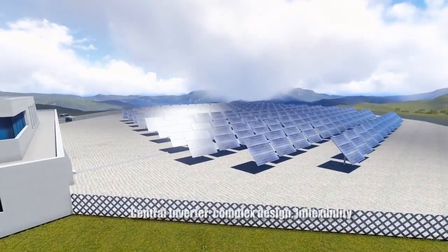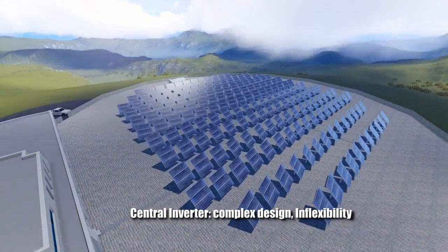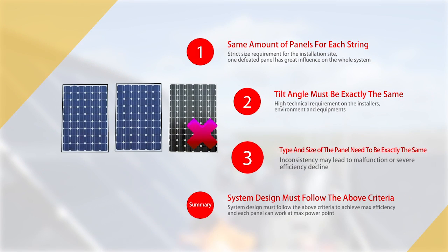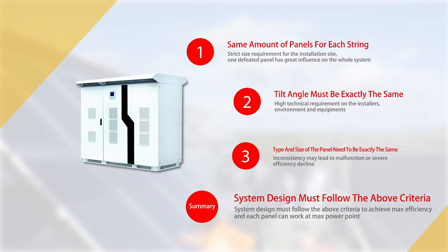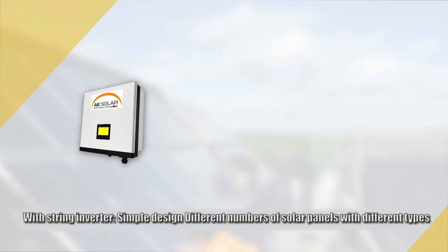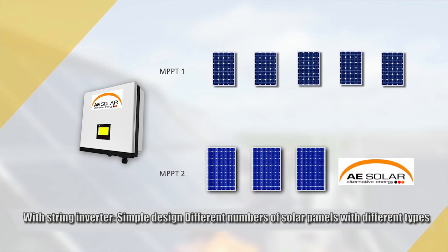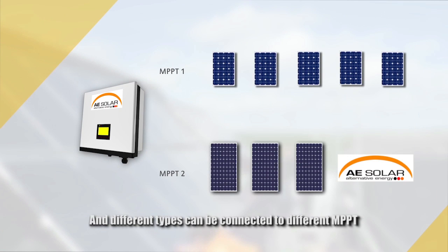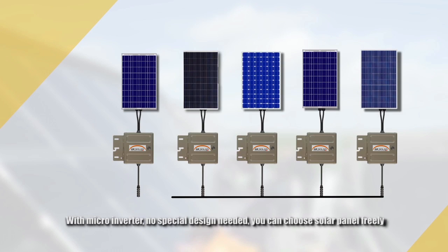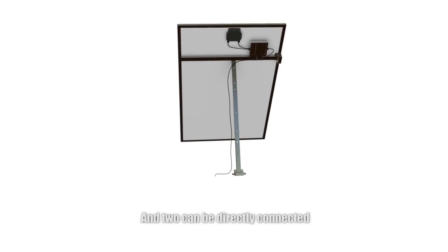Flexibility in system design: central inverters require complex and inflexible design — to ensure each string of solar panels works at the maximum power point, the number of panels, tilt angle, panel type, and size of each string must be exactly the same. With string inverters, the design is simple — different numbers of solar panels with different types can be connected to different MPPTs. With microinverters, no special design is needed; you can choose solar panels freely and they can be directly connected.